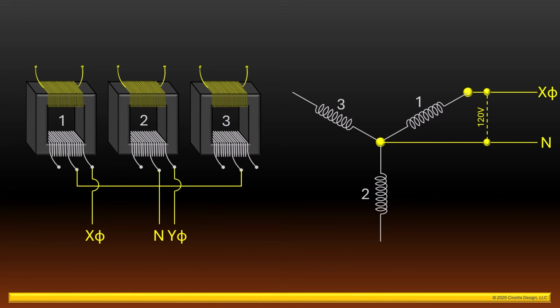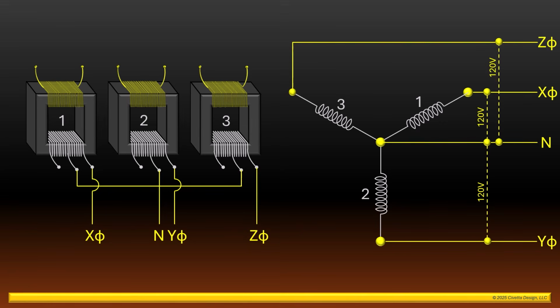We'll then connect the Y phase lead to the same position of the middle transformer, which creates another 120 volt potential to the neutral. Finally, we'll connect the Z phase lead the same way, creating another 120 volt potential to the neutral. If you remember from the previous video, the delta connection only provides single-phase 120 volt power across the windings of the middle transformer. This Y connection produces the same 120 volt power, but it does so across all three transformer windings.